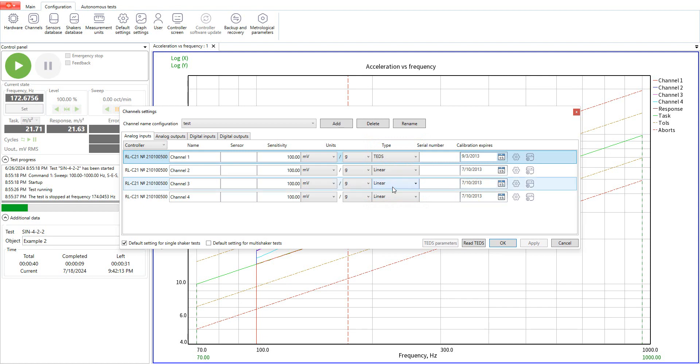A TEDS sensor has an embedded memory which stores the results of the latest calibration, for instance its sensitivity. If you select TEDS and it is already connected, the system will read the information from the sensor automatically and the sensitivity will appear in the field.